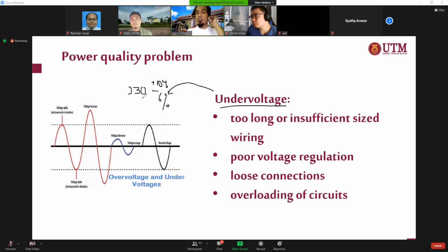If your voltage level is still within this range, we won't call this value an under voltage. Under voltage means it must be below minus 6% of the 230 volt, not 6 volt. So in this example, this is the normal voltage, and suddenly you have this lower voltage. We can call this under voltage, as long as it is less than -6%.